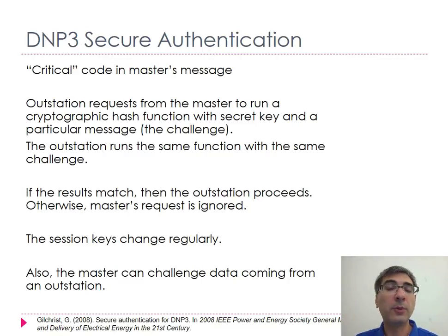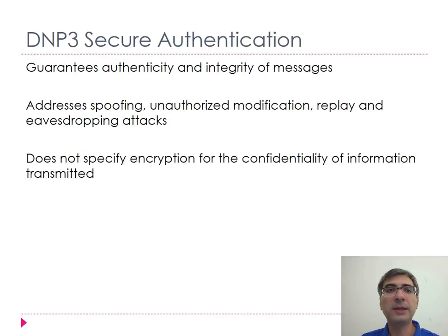Now, of course, if that works well, then the outstation does what it is requested to do. The session keys change regularly. So, for example, they might change every 15 minutes. And interestingly, the master can also request outstations to prove that they are the real outstations, that they are authentic, that they are not rogue outstations in a sense. So what this means about the DNP3 secure authentication is that it guarantees authenticity and integrity of messages. So the messages are authentic and they have not been modified in an unauthorized way by some kind of attacker.